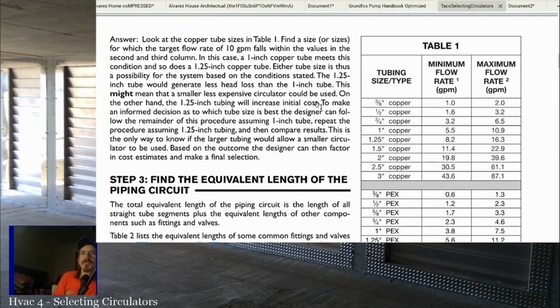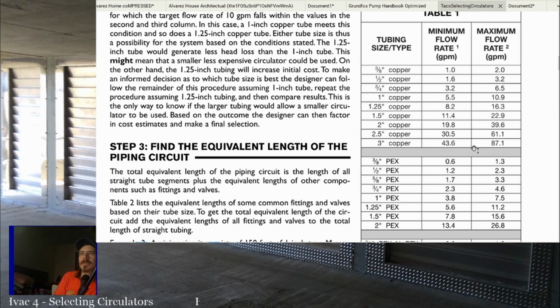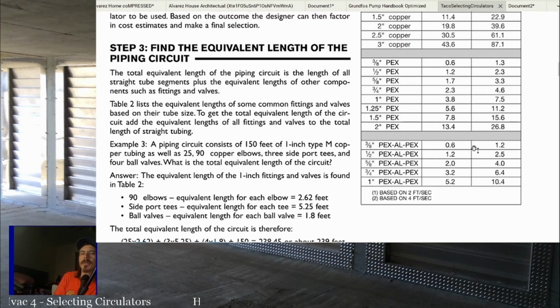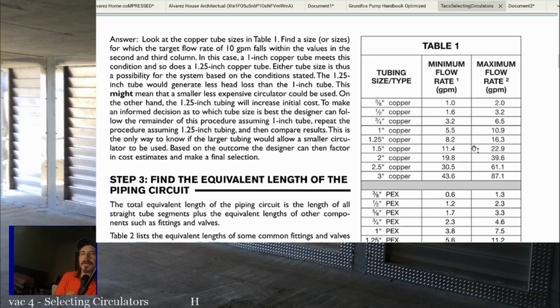All right, so look at the answer. Look at the copper tube sizes in table 1. So these are your tube sizes. And I know it doesn't show black pipe here, but black pipe is relatively close to copper, so you can use that as an estimation if you're using black pipe. Black pipe is going to have slightly more loss. It's going to be slightly below this, but I found that if you figure copper there, it's pretty close.